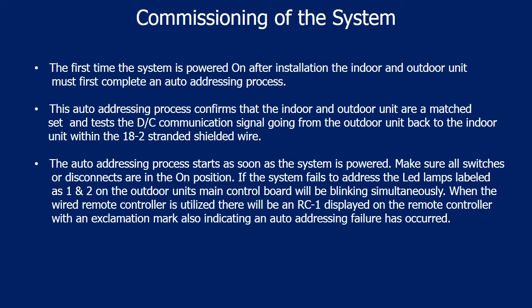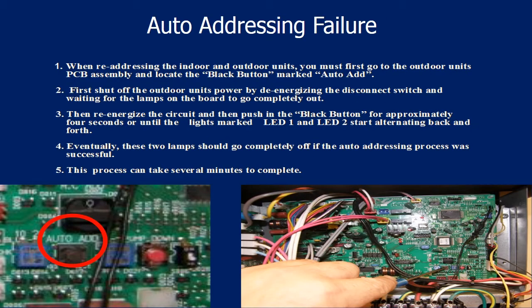If the system fails to address, the LED lamps labeled as 1 and 2 on the outdoor unit's main control board will be blinking simultaneously. When the wired remote controller is utilized, there will be an RC1 displayed on the remote controller with an exclamation mark, also indicating an auto-addressing failure has occurred. In the event the system fails to auto-address the first time, there is a manual procedure which can be initiated from the outdoor unit's main control board.